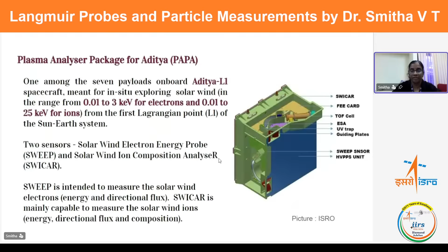You can see that there is an electrostatic analyzer section and there is a time of flight section and all that. And the UV trap is there because we do not want secondary electrons generated by the UV falling on the instrument. So that we will know once we talk about the detection. So the detectors basically, as I told here, one of these detectors very widely used is the MCP. So how the MCP works is as follows.